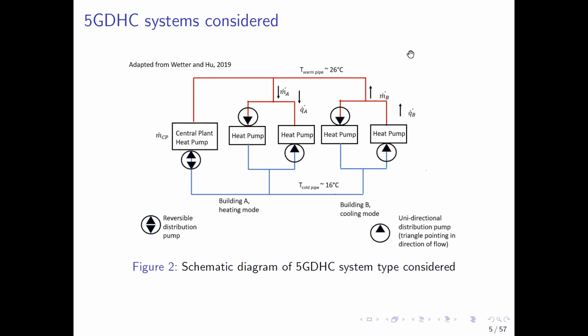And 5G DHC systems can operate in a variety of configurations. I focused on systems with parallel connections of loads to the network, meaning that each load effectively sees the same supply temperature from the network and the same return temperature, in that in this case, the mass flow through the energy transfer station connecting the load to the network is controlled to a fixed delta T. But in principle, such systems can operate with loads connected in series, in a single pipe network configuration, and in a configuration with unidirectional mass flow.